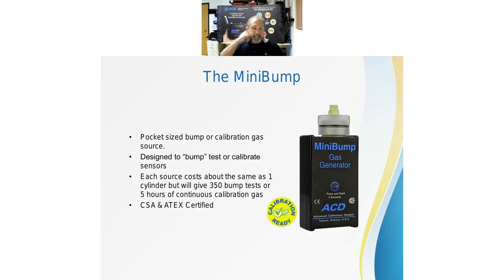We also have some bump testing instruments. Depending on your safety person at your facility, a lot of people will calibrate at a set time interval, maybe every quarter, every month, every year. And in between, they'll want to bump test or functionally test the sensors to make sure they're working. So this little instrument here can do either. It can either be a calibrator or it can be a bump tester. The sources that go inside of these will last for 350 bumps or 5 hours of continuous calibration gas use. And this one has CSA and ATEX certification as well, so it can be used in a hazardous location if needed.